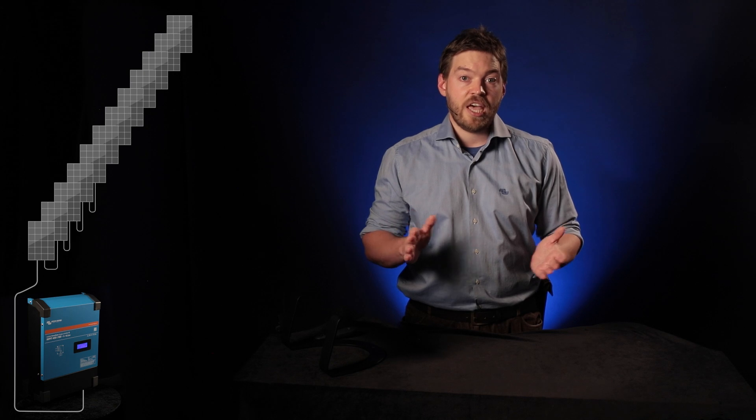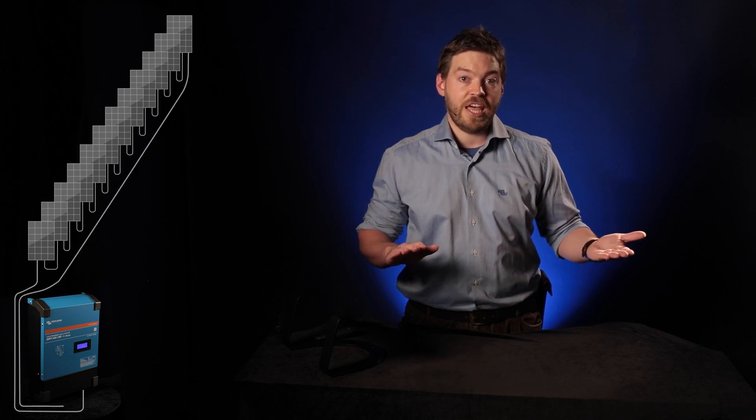The increased voltages improve efficiency on the panel design and installation side. You can run much larger strings of panels together up to 450 volts that reduces wire size and increases the length of run you can have reducing current. It also makes the installation quicker for the installers.